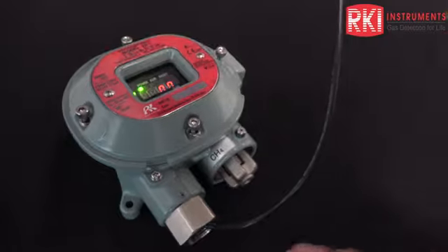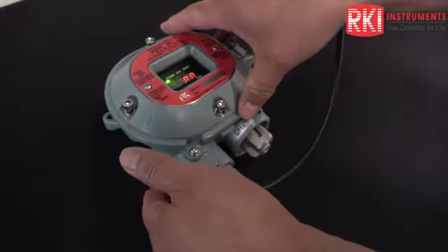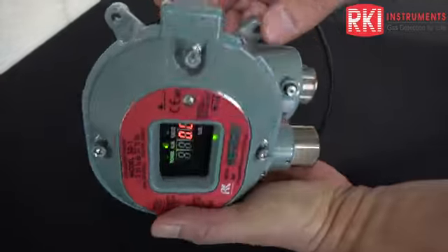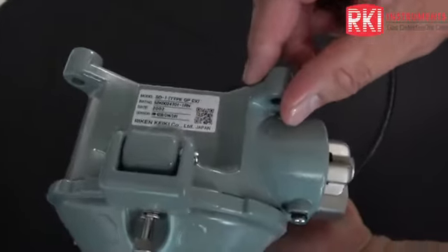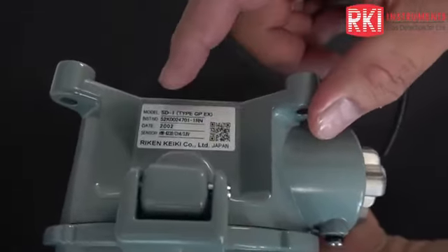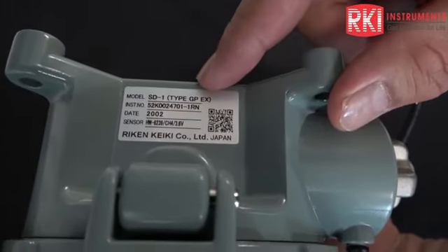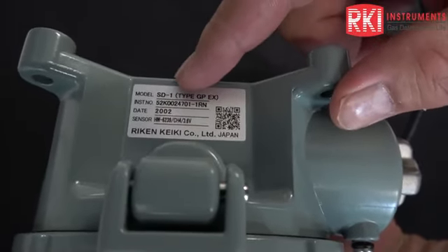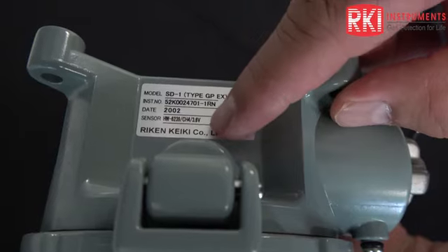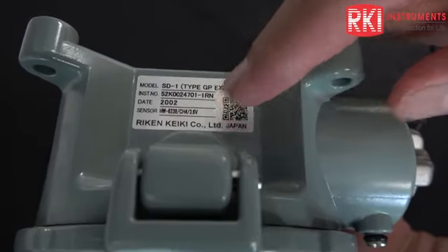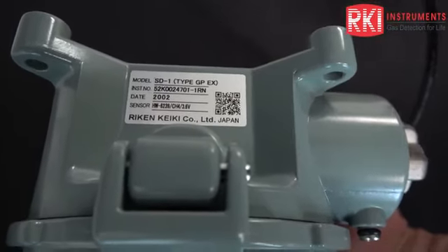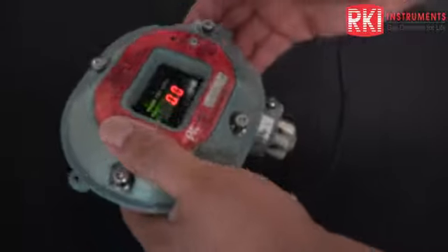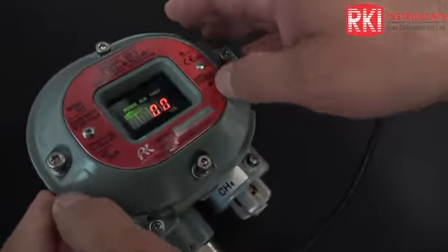All right, let's take a look at the detector head in general. I want to point out that you've got some label information on this side. So it gives you the model number, the instrument number or serial number, and also the date of manufacture, and then the gas that it was originally set up for. In this case, there is a CH4 there. And then the sensor model number is also there.